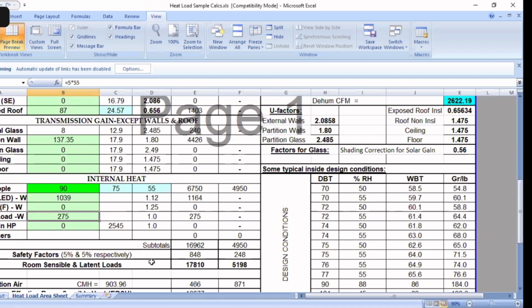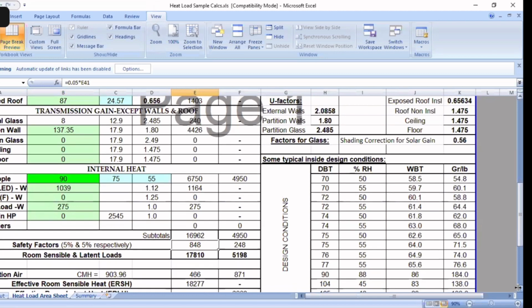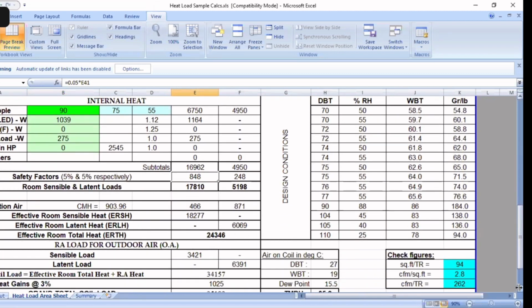So for all these things, I have considered a safety factor of 5% on both sensible and latent heat. This safety factor is mainly to take care of system heat gain, duct system heat gain, and fan heat gain, AHU fan heat gain, etc. So this 5% is added, and this was the effective room sensible heat. This is the effective room latent heat.